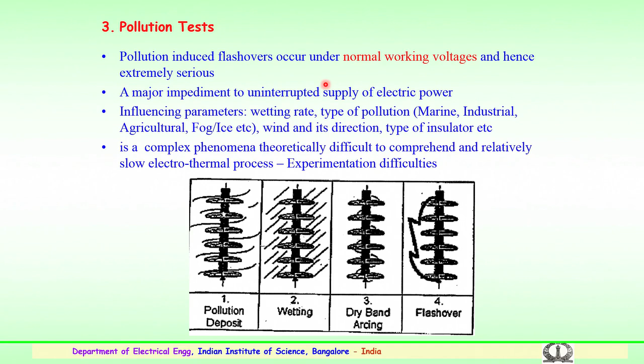This is a general arrangement where two methods are employed as per IEC 507 or 60507. One is the salt fog method, the other is the clean fog or solid layer method. These are described in the standard and are the outcome of several research and standards organizations like IEC, IEEE, ANSI and CIGRE working groups, who have worked for more than 50 years and come up with two procedures for ceramic or glass insulators.